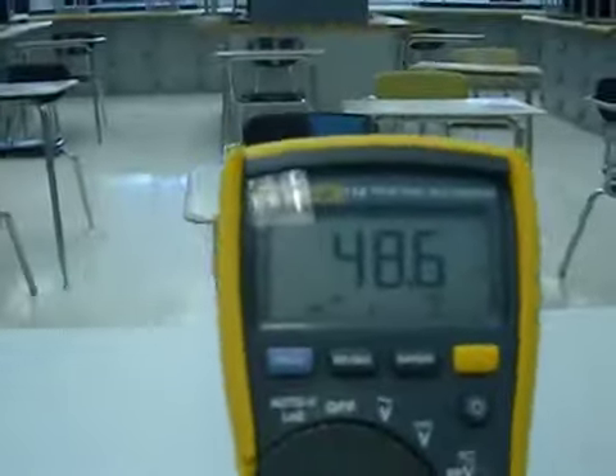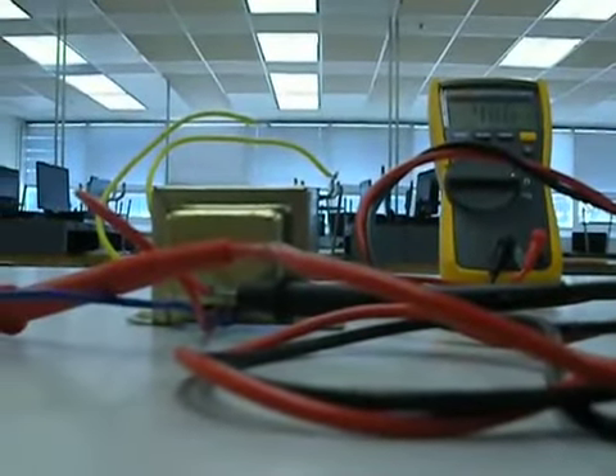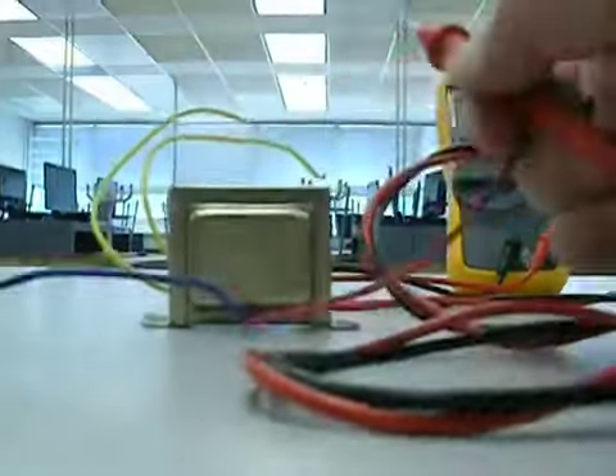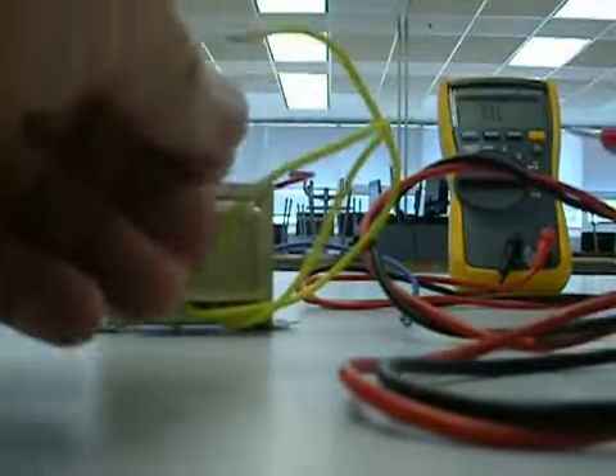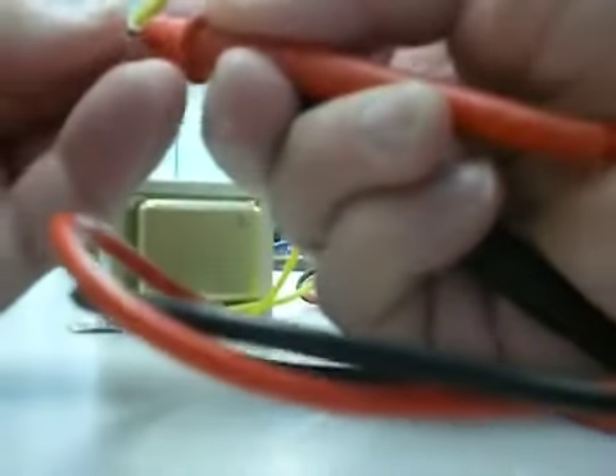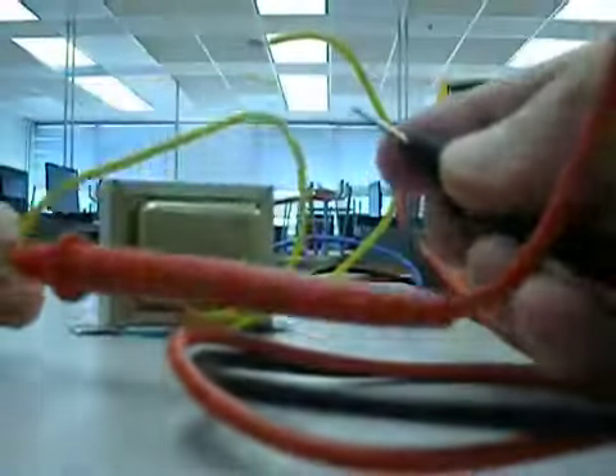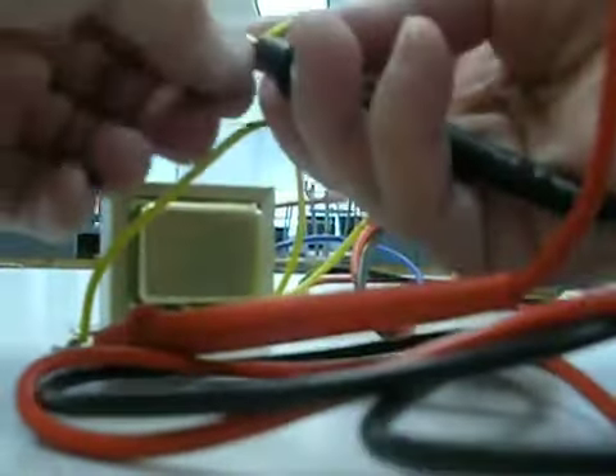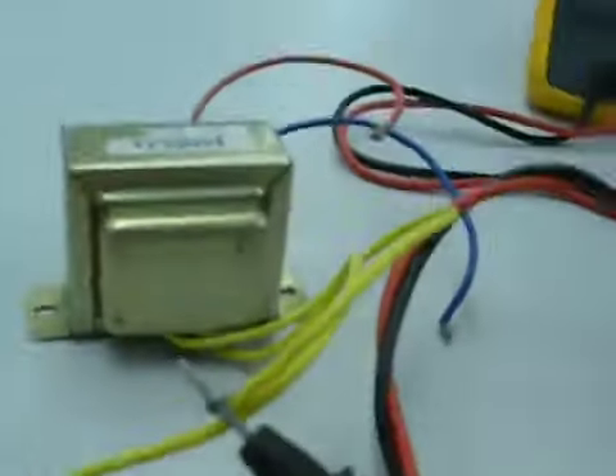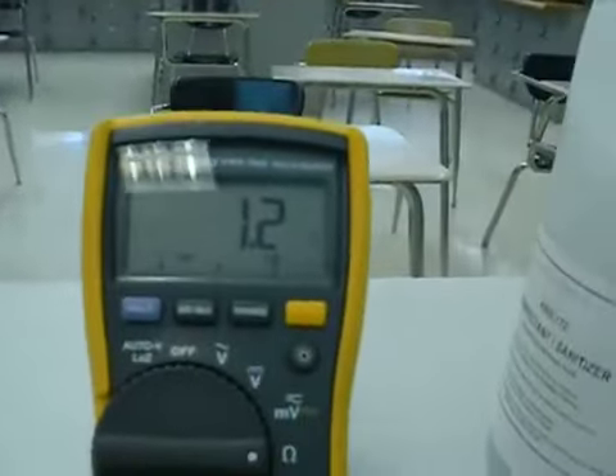Yeah, see right there, around 50 ohms, a little bit less. So that's my primary reading. Then I want to move the meter leads, and I want to connect them up on the yellow wires. That's the secondary wires. And get my secondary reading. Yeah, I got my secondary ones hooked up. And it's about 1.2 ohms.